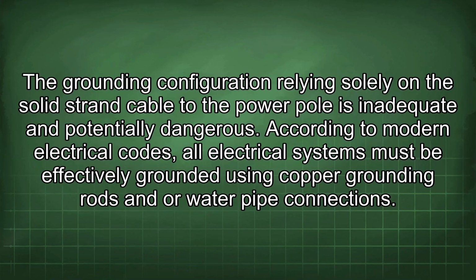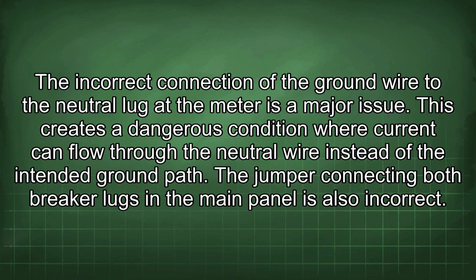Grounding configuration relying solely on the solid strand cable to the power pole is inadequate and potentially dangerous. According to modern electrical codes, all electrical systems must be effectively grounded using copper grounding rods and/or water pipe connections. The incorrect connection of the ground wire to the neutral lug at the meter is a major issue. This creates a dangerous condition where current can flow through the neutral wire instead of the intended ground path.